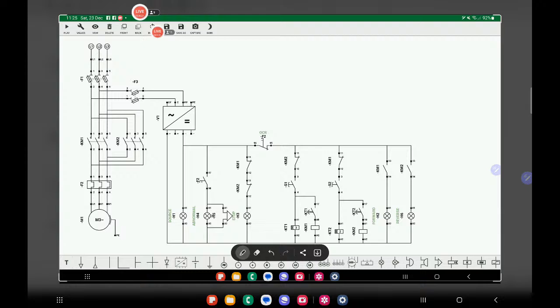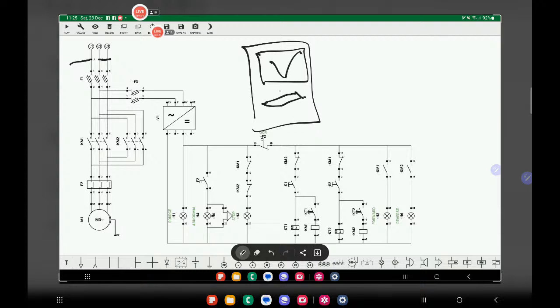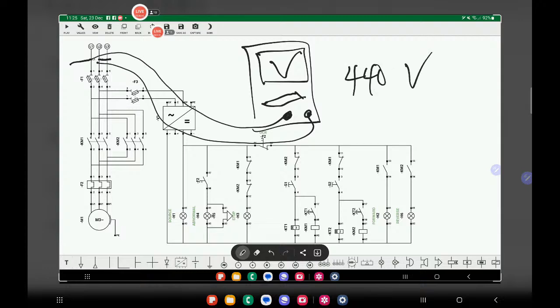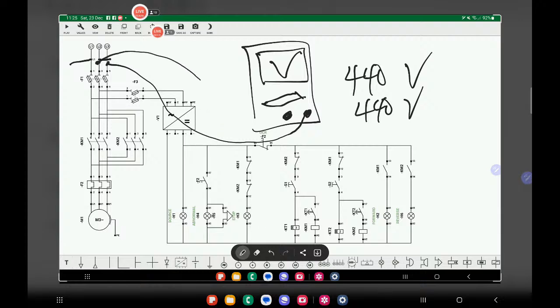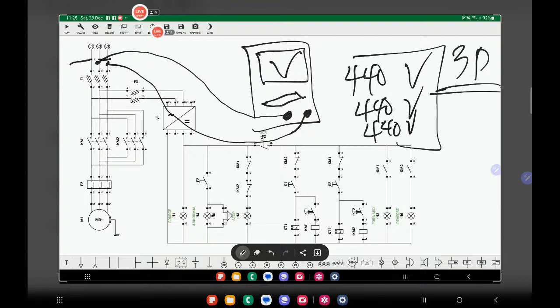For sure, you'll measure each phase. Let's say you have your multimeter set on AC volts. You'll measure line 1 and line 2, and you'll have 440 volts. Then I'll move the other probe onto line 3, and I should have 440 volts. Then I'll move the other probe onto line 2, and I should have 440 volts. In this way, you'll have a present 3-phase in your system.